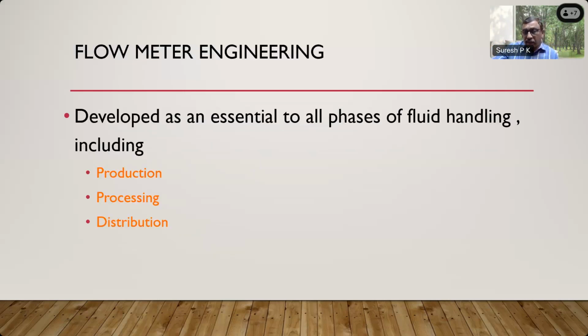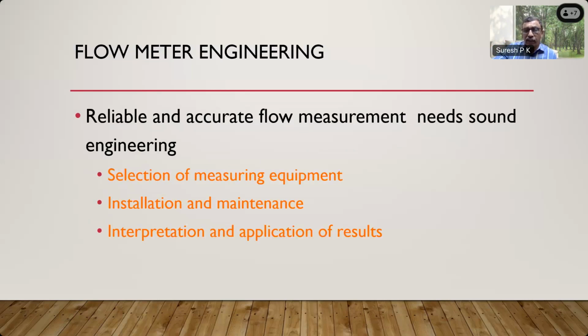Flow metering is involved in production, processing, distribution, all these things. A reliable and accurate flow measurement needs sound engineering practices: selection of measuring equipment, installation and maintenance, interpretation and application of results. Like selection of measuring equipment, I'll tell you an example. If you have a pipeline which is coming from the top, say by 3 meters, it comes down and then it takes a sharp turn at the bottom of the 3 meters. Immediately after the turn, you place a flow meter, a turbine flow meter, and try to measure the flow. You will not get the flow accurately.